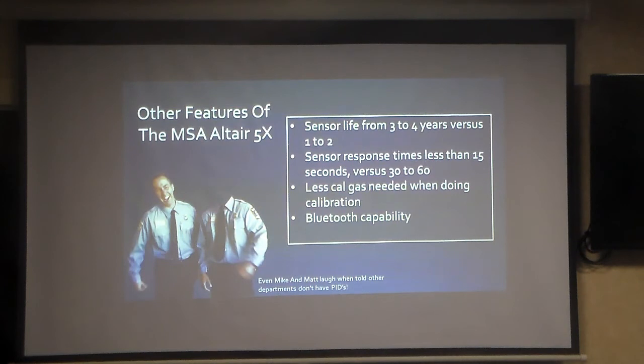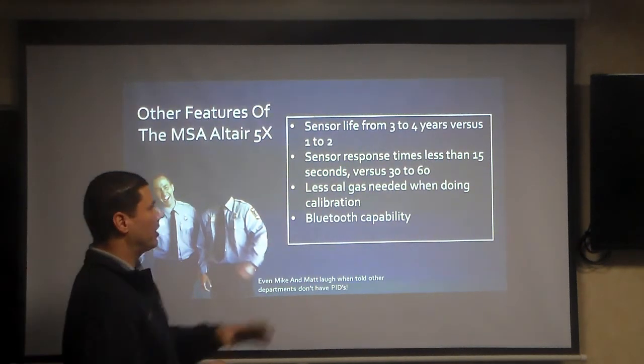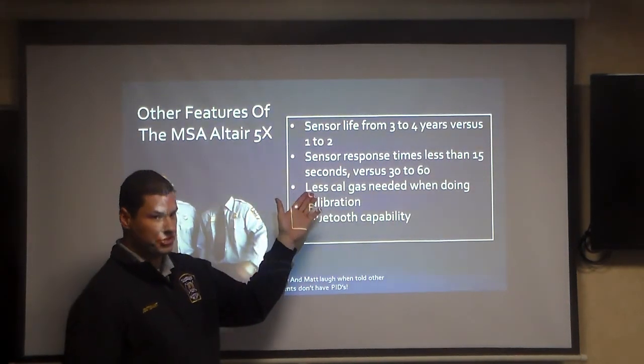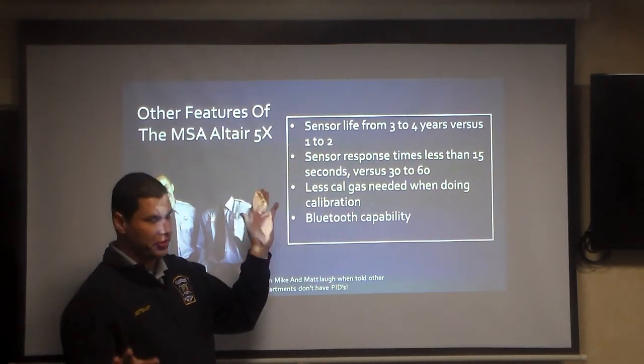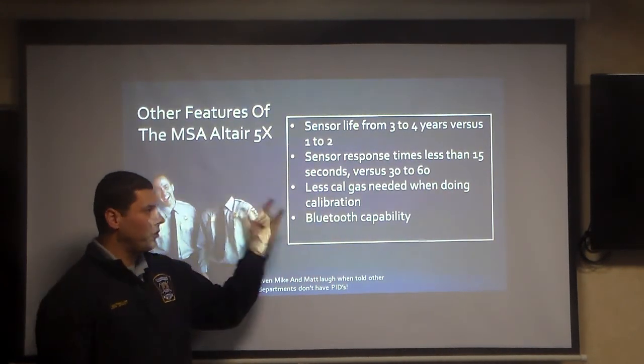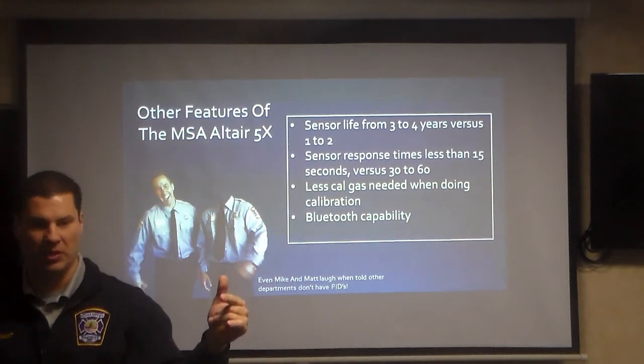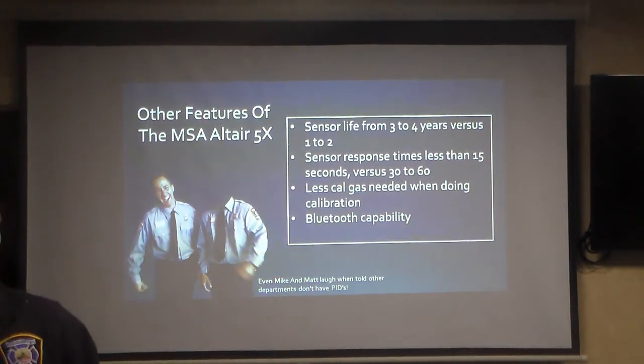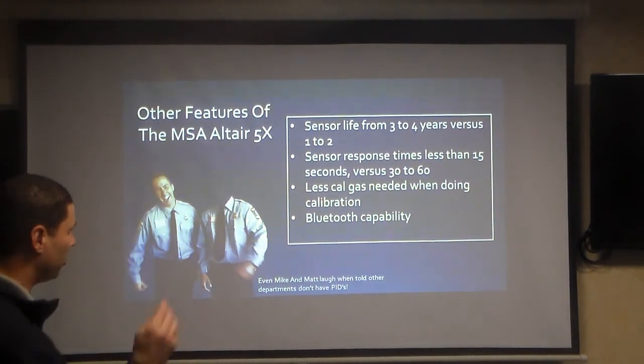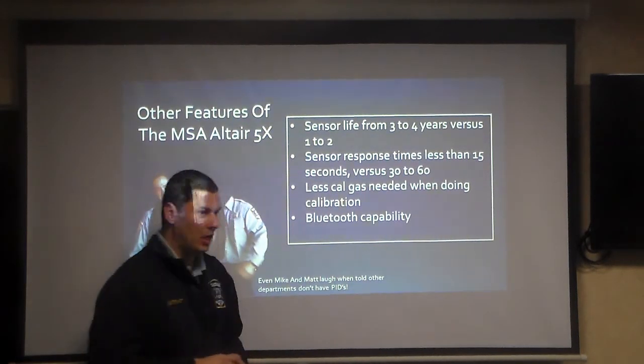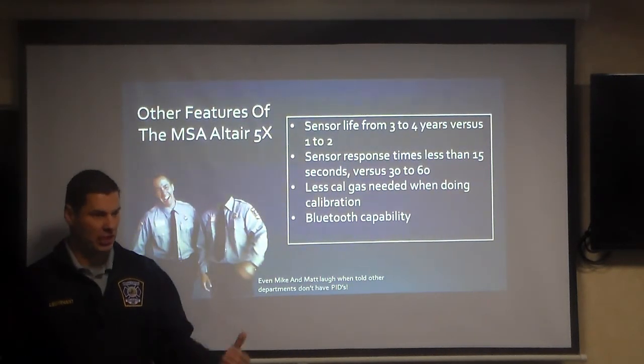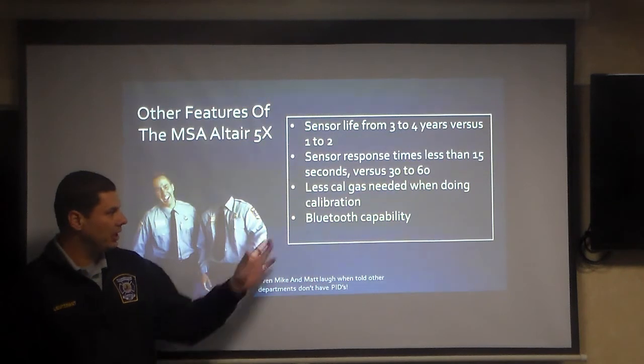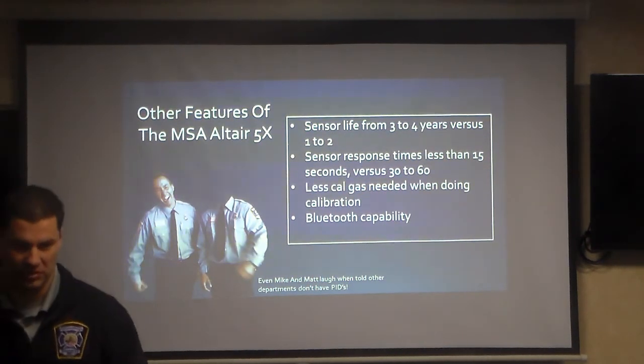So the difference specifically is, I already talked about the sensor life. We have an increase in the sensor life to about 3 to 4 years, it varies on the sensor. We all know that the old meters are supposed to be in the room for about 30 to 60 seconds to get a full reading. Not anymore, you got 15 seconds. The calibration is a lot easier, it uses a lot less calibration gas, and there is some Bluetooth capability to this meter.